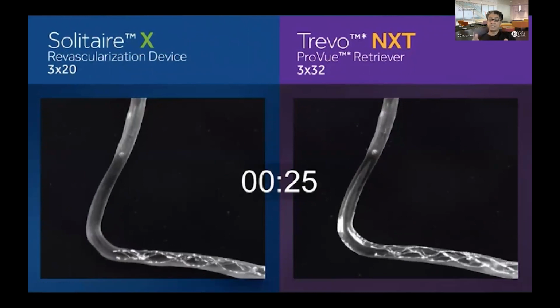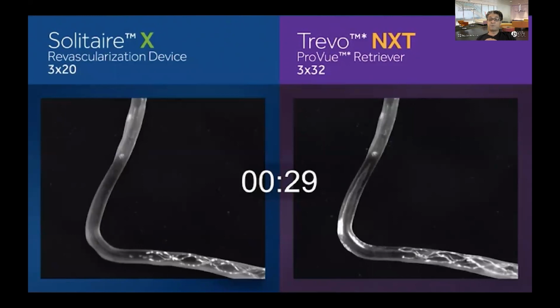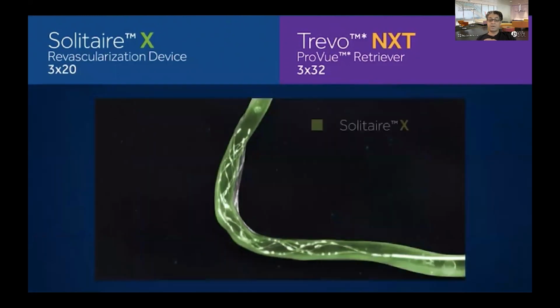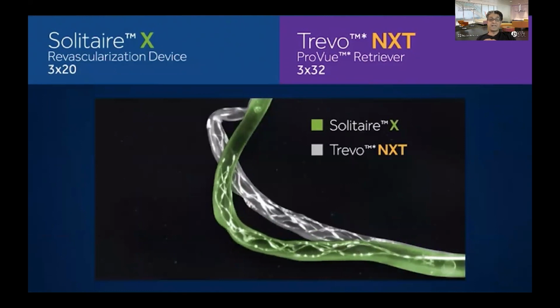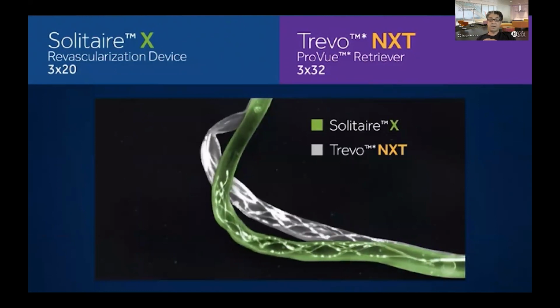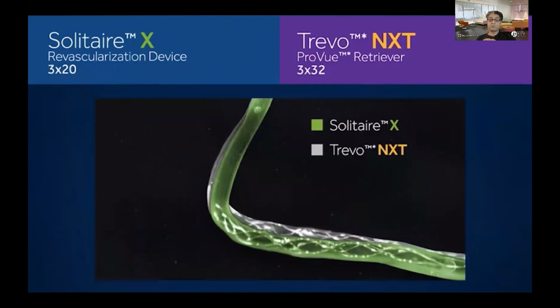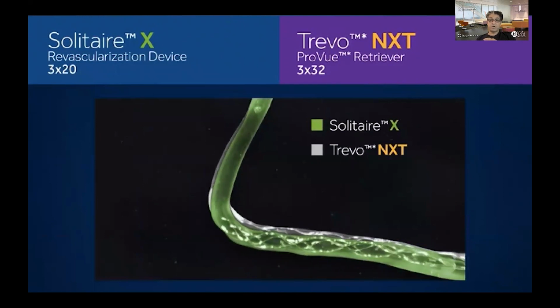So this in vitro test would suggest that the deformation of vessels inside the body during retrieval is a lot less with the Solitaire, likely related to its parametric design and reduced radial force compared to the Trevo, which is the traditional cylindrical device.